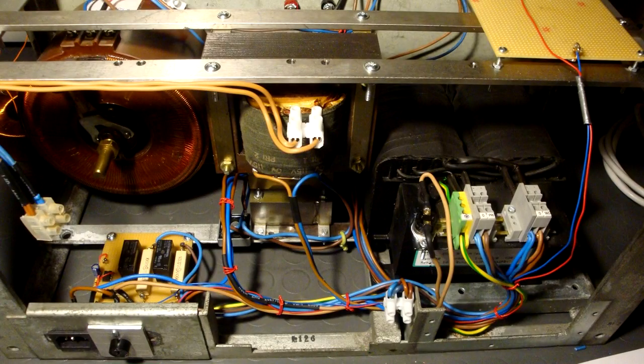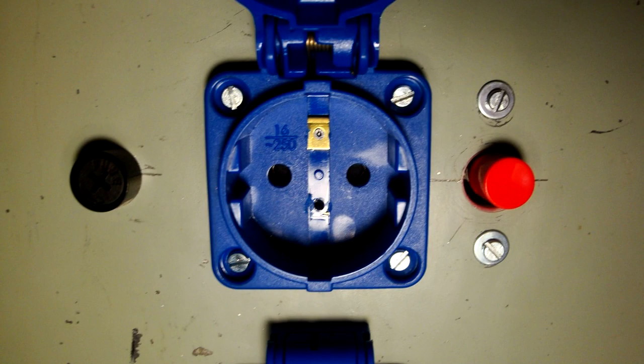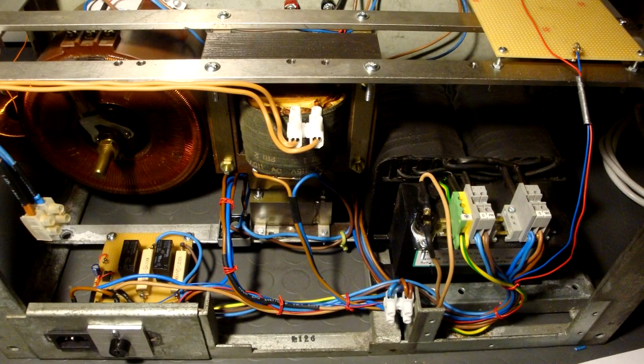I connected the metal parts of the enclosure with a protective earth, as it is common practice with stationary units. The sockets on the front panel, however, are not to be connected to the PE. In fact, I even removed the earth connectors from the sockets entirely. I then added several fuses and a temperature switch which sits on the core of the 1 kVA isolation transformer.